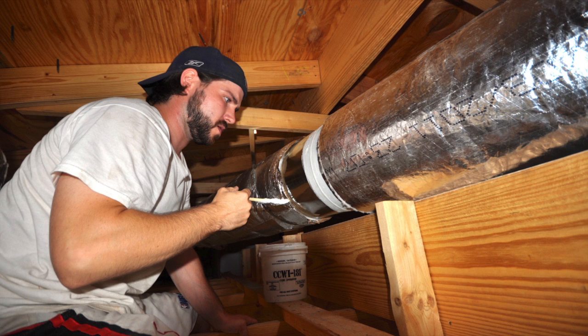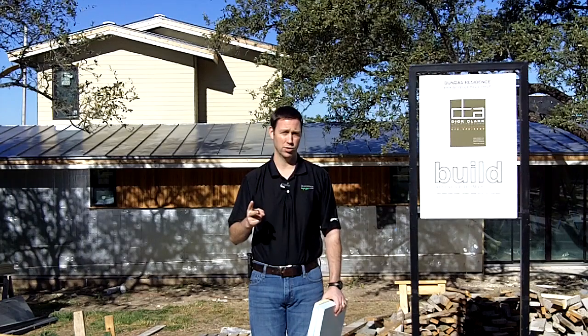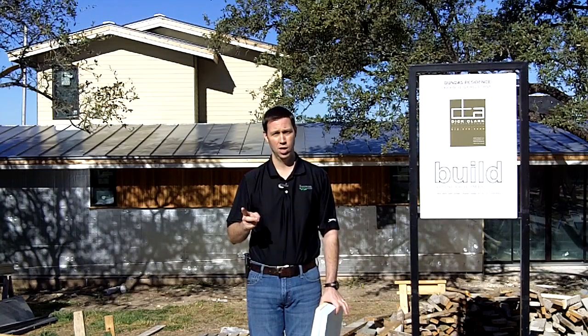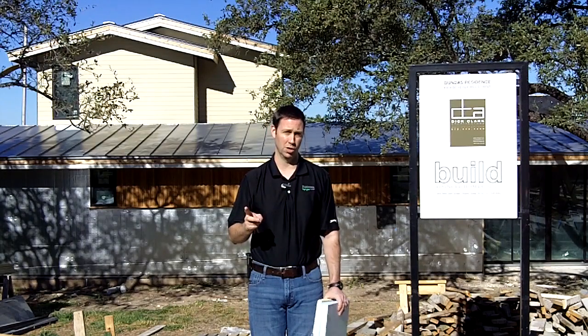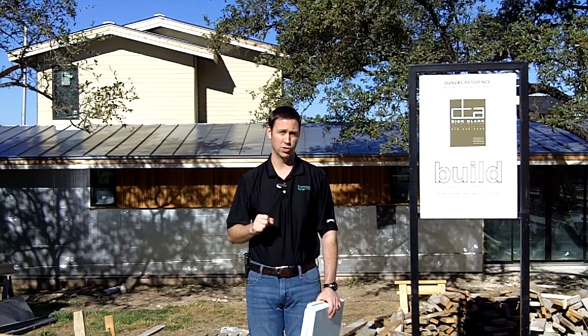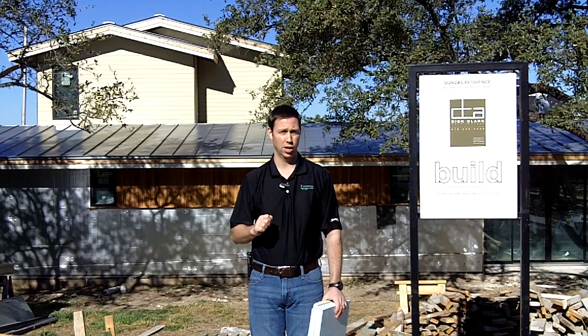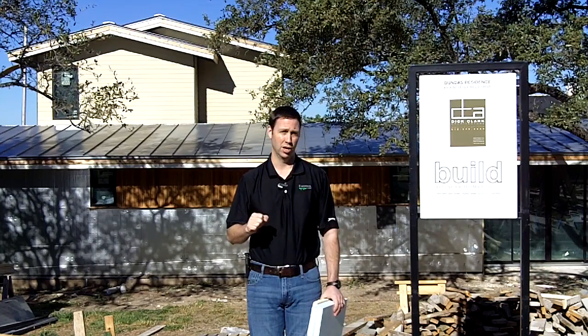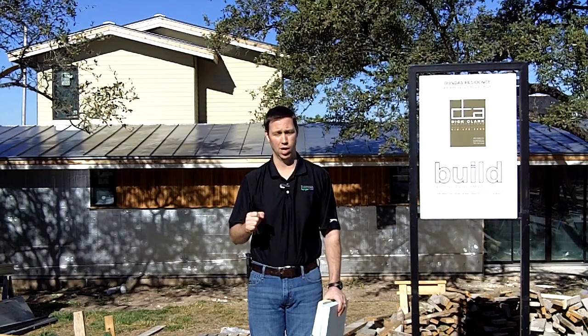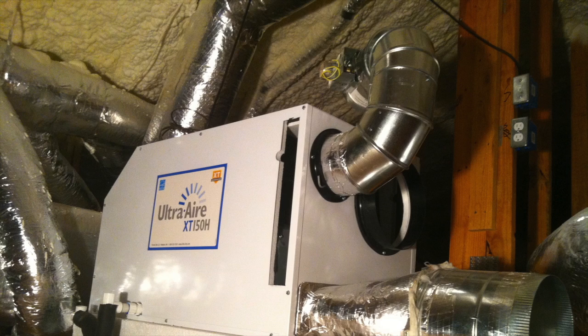We're adding all-new rigid metal ductwork — check out some of my other videos to see how we want to do that correctly. We're doing two brand-new systems. We've got a Mitsubishi low-static-pressure variable refrigerant flow system upstairs — that's a 20-plus SEER system, an incredible system, basically a form of a mini-split. The second zone, which is the largest zone, is an American Standard gas furnace, 95% efficient, coupled with a 16-SEER two-stage compressor on the outside. And lastly, when we talk about comfort in this Texas climate, it's very important to put a dehumidifier in this house — we're using an Ultra-Aire, I believe this is an XT150, going in this house.